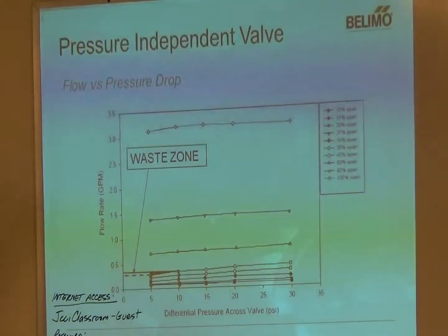Now we're going to look at the same type of graphic, but with a pressure independent valve. So you can see here now, with this graphic, the scaling is different, just so we can show that there is a small waste zone, but it's much smaller than the pressure dependent. So between that 5 and 10 pound change in differential, we have maybe 1/10 of a gallon change in flow. So obviously a much smaller waste zone using pressure independent valves.